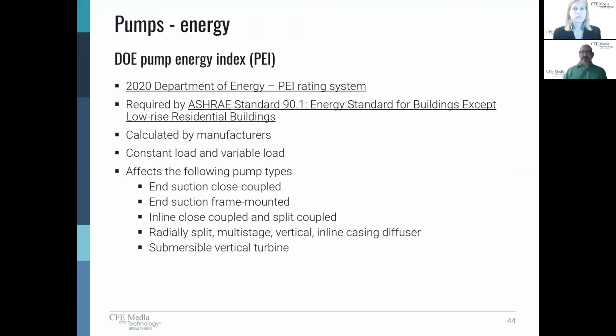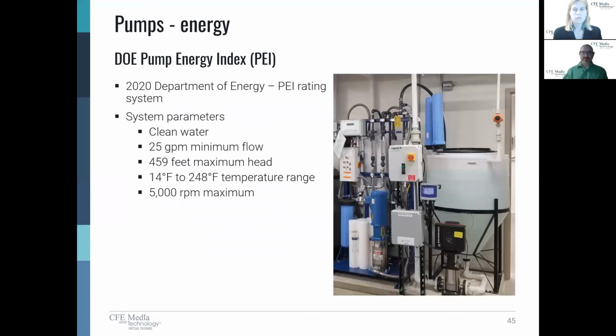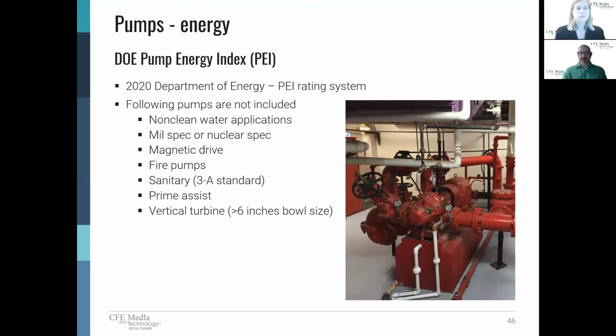We're not going to spend a lot of time on the Department of Energy Pump Energy Index, but it's important to understand that it affects a variety of pumps. So I have 3 slides here that we're going to go through fairly quickly. Understand that it was developed in 2016, and it took effect essentially in 2020, January 1st. It affects a variety of pump types, and it also has a variety of system parameters. So whether or not your pump is required to meet this requirement is going to be based on the type of pump that it is and the actual operational parameters of that pump. And luckily, it doesn't include every pump. There's a variety of pumps that don't have to comply, and one of them being fire pumps, like the fire pump we see shown here.